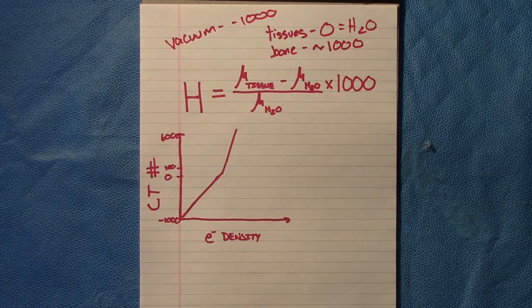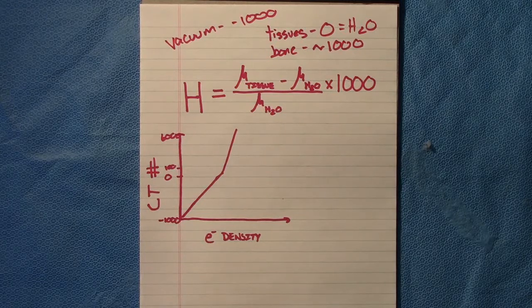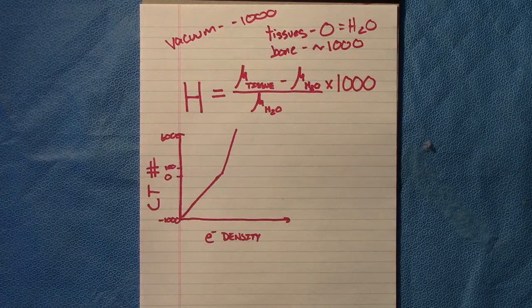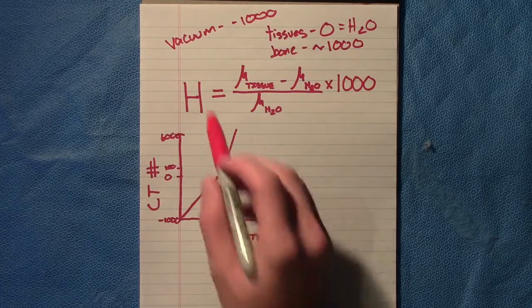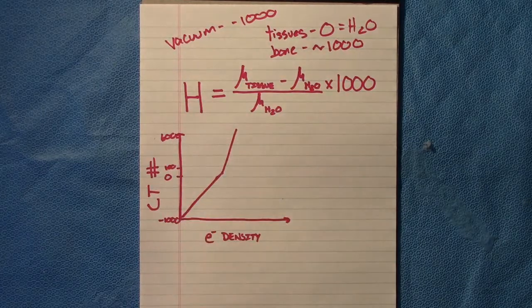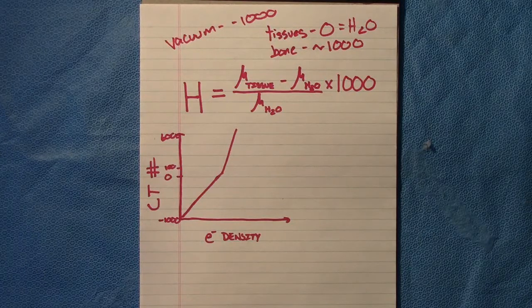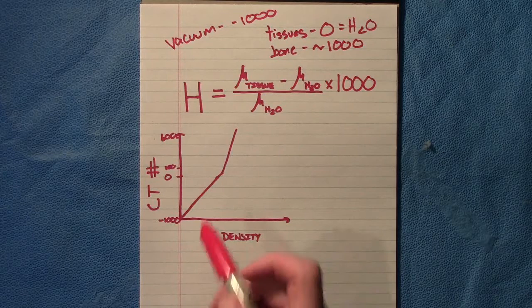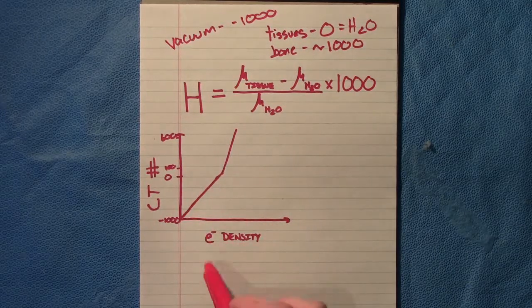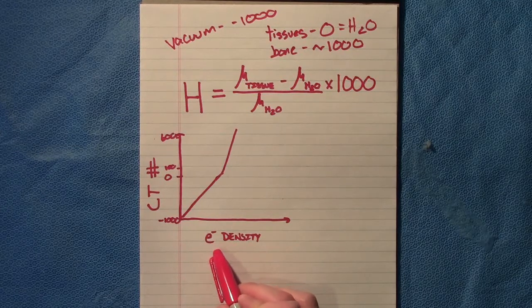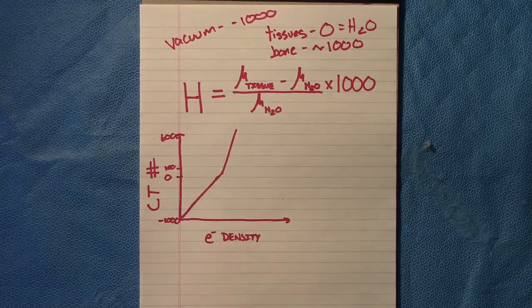To calculate dose for radiotherapy, the first thing we have to do with our CT is find these Hounsfield units for all materials, and we use that using a Gammex phantom. Because finding a CT number is great, but actually what we really want is our electron density, and we're going to use that for our heterogeneity corrections.